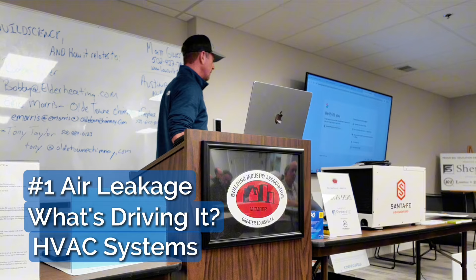But a lot of times you don't have a dedicated return in that bedroom. You might have a transfer grill that's going through the wall or the door. Maybe you have a jump duct. But even if you have a dedicated return in that bedroom, perfect example is a master bedroom. Usually you're going to have way more supply air going into that master bedroom than you're going to have return air going out.